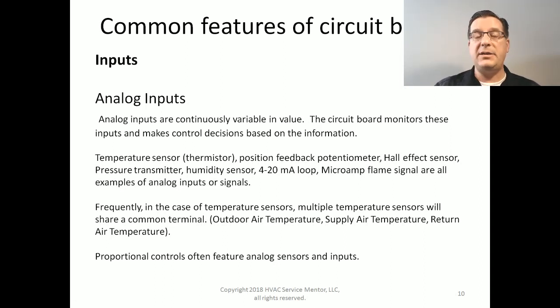Another type of input, the second major type, is called an analog input. Analog inputs are continuously variable in nature. Earlier, when I was talking about the digital binary inputs, I was saying it's either this or that, no in between. Analog inputs are exactly the opposite. There is all in between. It isn't either all or nothing with an analog input. It's always going to be a variable input. The control board is going to monitor these inputs and make controlled decisions based on what those inputs are.